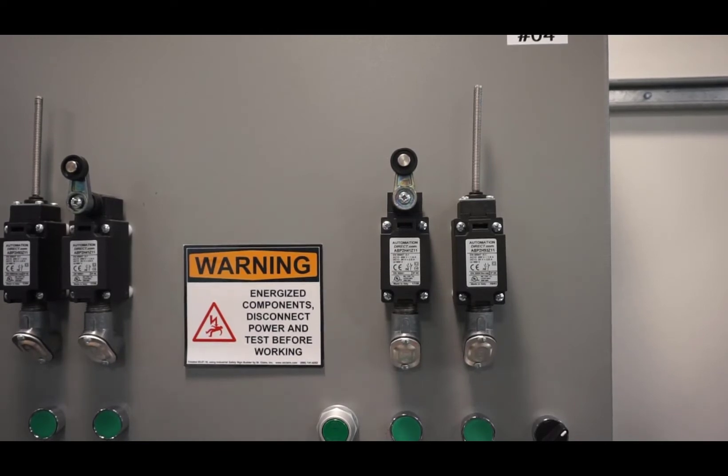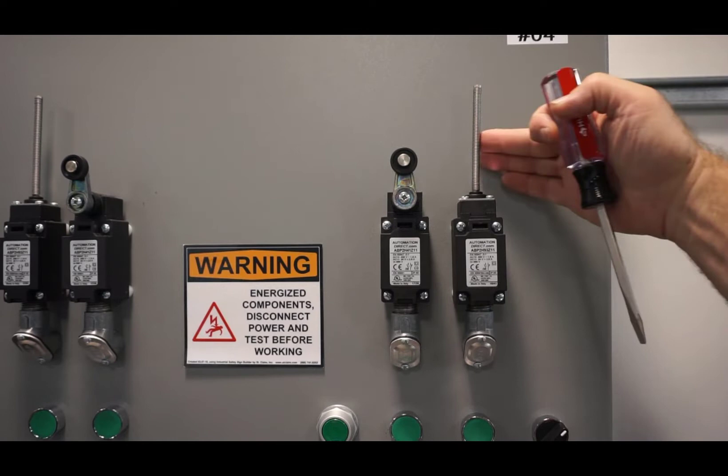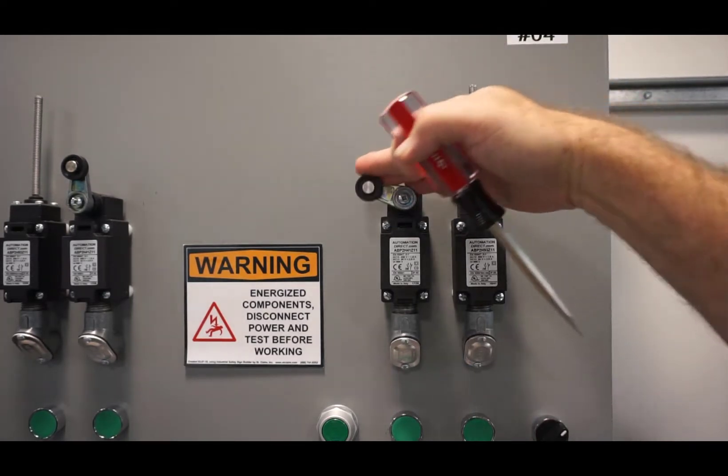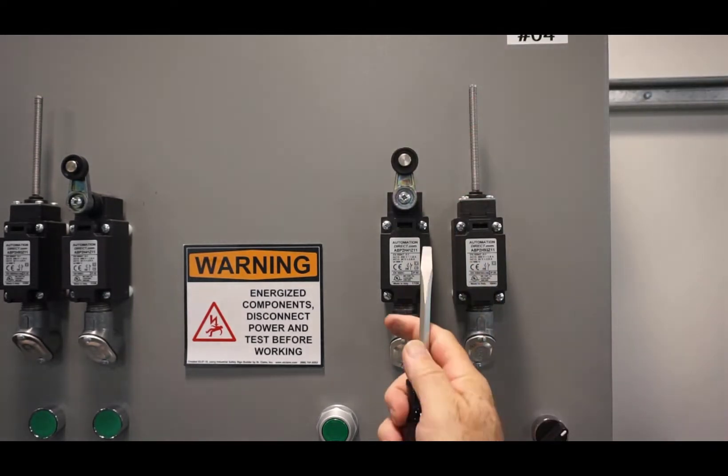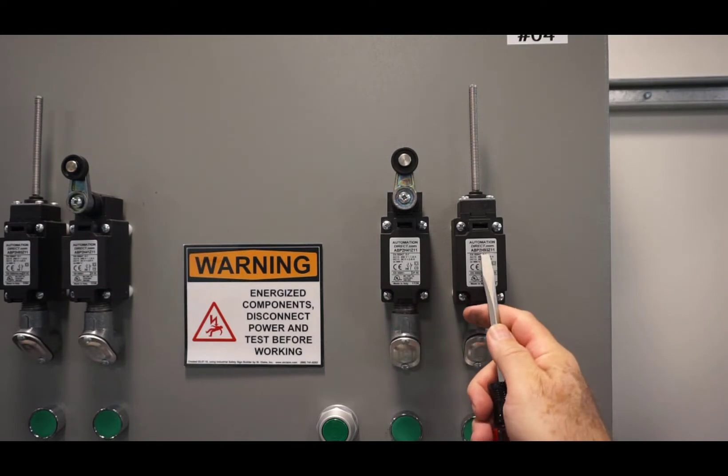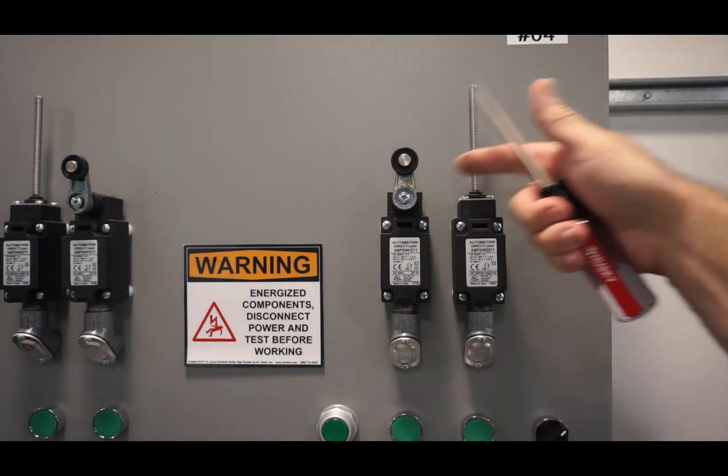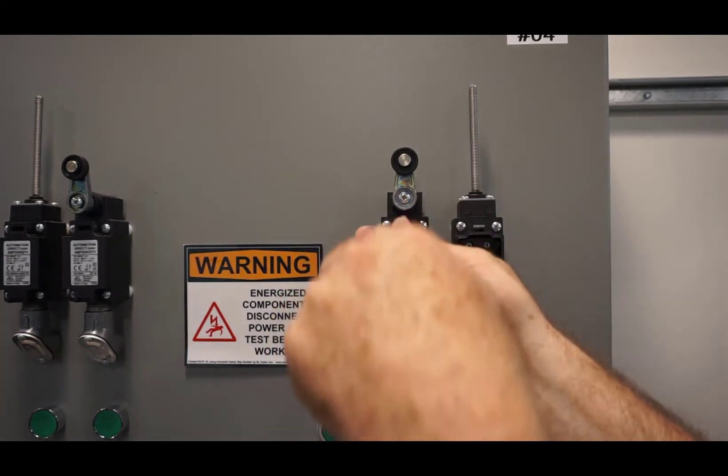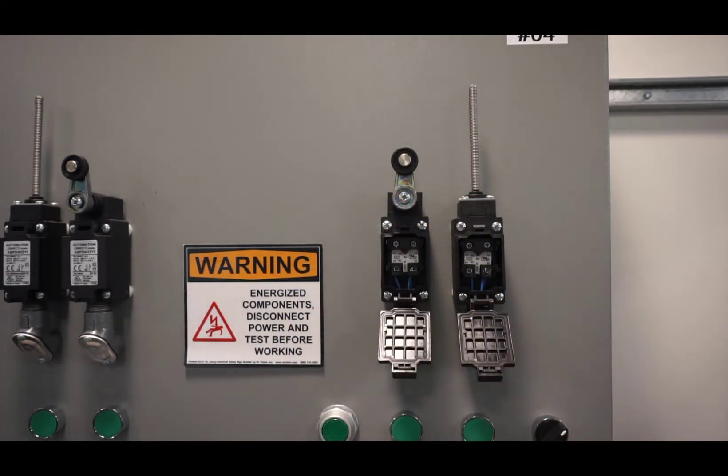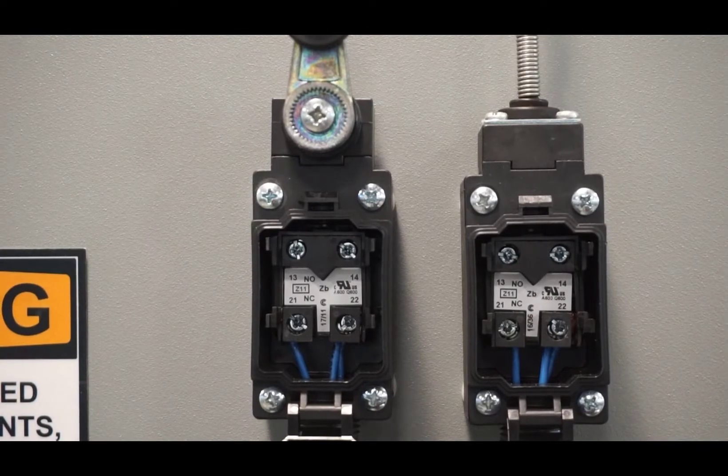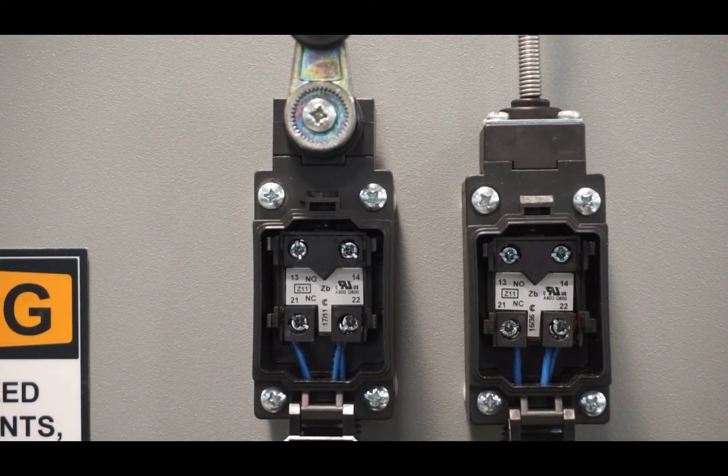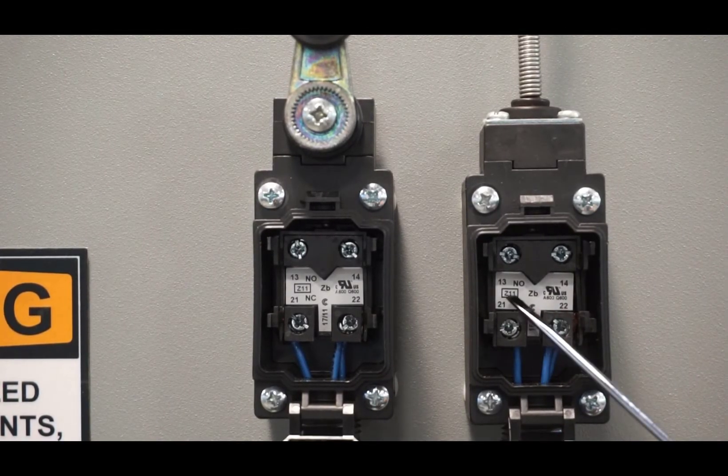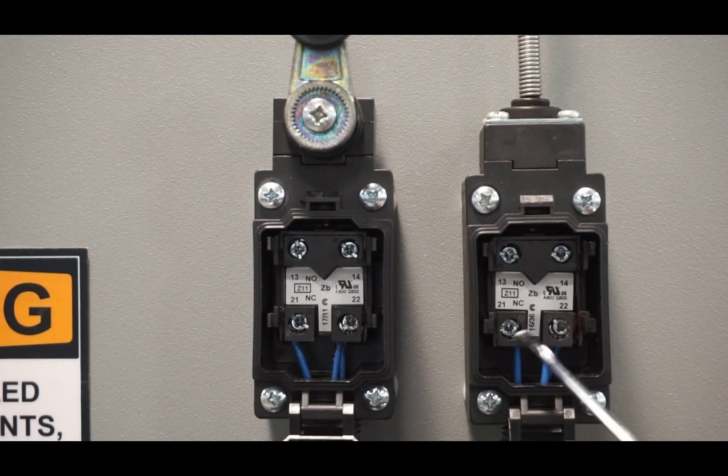Here's your limit switches. The limit switches are the same part number. The actuators, roller actuator and whisker actuator are different part numbers. They open up with a screwdriver, just pop it open. You can see here 13 and 14 are the normally open contacts, and 21 and 22 are the normally closed contacts.